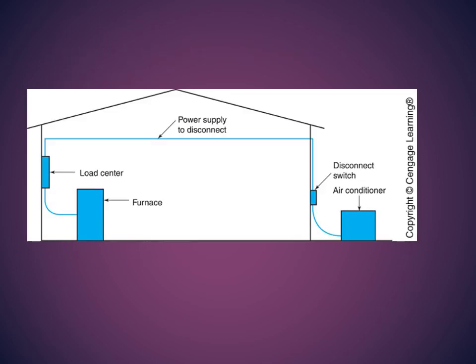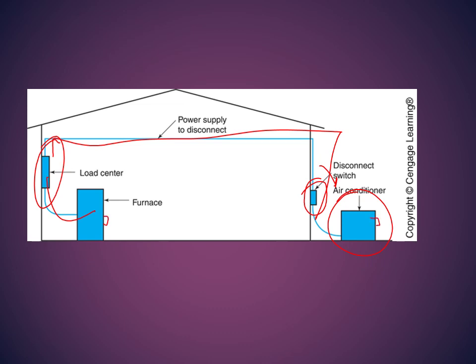So this picture will show you how we connect equipment from a load center. This is my control panel or power supply center that goes all to the furnace here, and the power line goes all the way to the outside unit. And again, if you notice, the disconnect switch is within reach. So if you're outside doing some repair and something sparked or something didn't seem right, you can go and disconnect the switch right away to the entire system going in here.